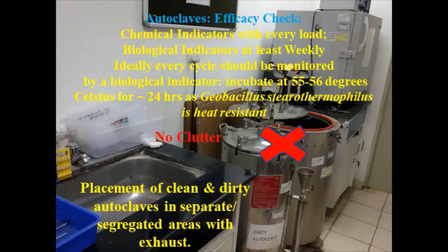And the autoclave efficacy, whether the autoclave is acting effectively or not, should be checked with chemical indicators with every load. There is a color change which is defined by the manufacturer. That color change should occur after the autoclave cycle to ensure that the autoclave cycle has been effective. And this chemical indicator should be used with every load, and the records of that should be maintained by the laboratory. And for biological indicators, the national guidelines say that the biological indicator should be used at least weekly.